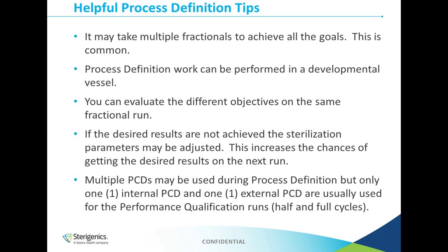Also, if you don't get the desired results on your fractional run, you can adjust those parameters for the next run to increase the likelihood of you getting the results that you need. Now remember, as you adjust the parameters in process definition, it does not mean you're adjusting the parameters in your half cycle and your full cycle. In the fractional, you're doing the objective of getting that growth. So you're adjusting those parameters and able to get that growth to do that comparison. You don't follow that through with the half cycle and the full cycle, because with those, you're using your actual proposed cycle parameters to get the kill that you need.